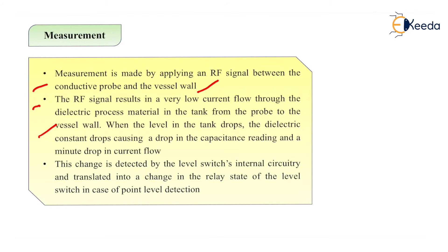When the level in the tank drops, the dielectric constant drops, causing a drop in the capacitance reading and a minute drop in current flow. This change is detected by the level switch internal circuitry and translated into a change in the relay state of the level switch in case of point level detection.